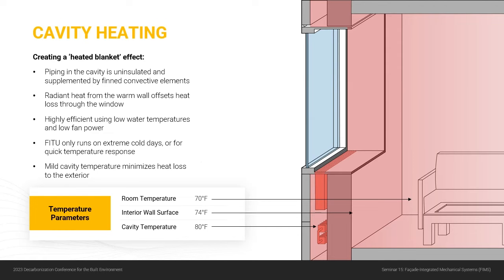Okay, so now we are going to get into some, I'm calling them more advanced concepts. So the first one is actually heating that cavity space. So if you think of insulating the building from the exterior like wrapping it in a blanket, now we'll think of it like wrapping it in a heated blanket. And it's relatively simple to do because we're running the pipework, the piping in that cavity. So if you simply leave that piping uninsulated, then it's going to give off heat into that cavity. That might not be enough heat, so you might want to add some convective elements to get more heat into that cavity, like the element shown in this image below, the FITU.